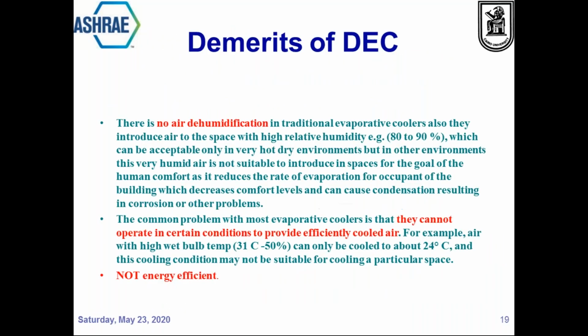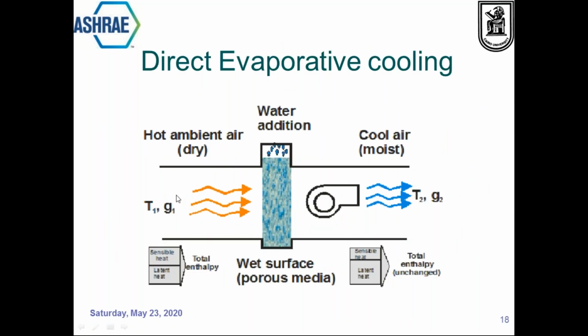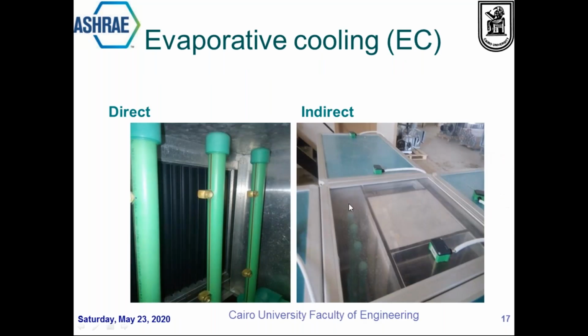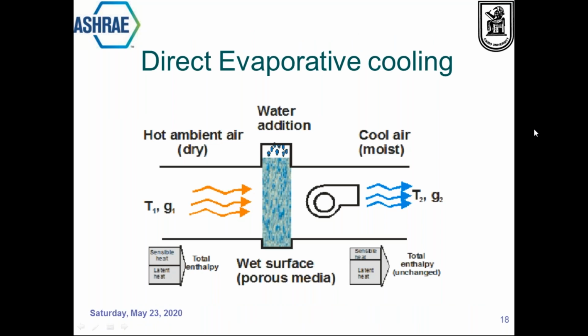So we built direct evaporative cooling and indirect evaporative cooling sections. In direct evaporative cooling, we spray water into the air, and in indirect we have a heat exchanger made of plastics or aluminium, where you can obtain effective cooling. In a sketch, here you have the hot ambient air, then the water spray in the direct way. We spray water directly into the air, and as a result, we get cooler air, but moist. It has a higher content of humidity.